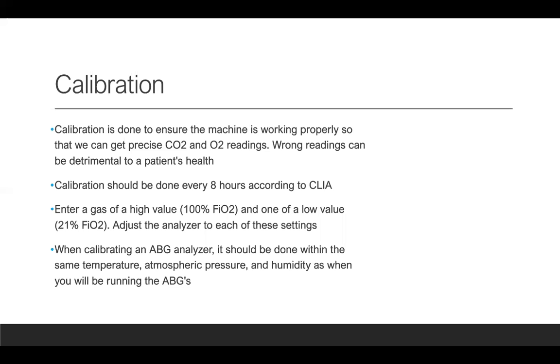Calibration should be done every 8 hours according to the CLIA. So it sounds pretty frequent, but like I said, the most important thing to do is to try and get that calibration done as often as possible. How the calibration works is you enter a gas of high value and one of a low value, and so the analyzer will adjust in between. So 100% FiO2, for example, and then another sample of 21%, which is our lowest percent of oxygen that we can administer. And then the analyzer will be able to adjust to those settings.